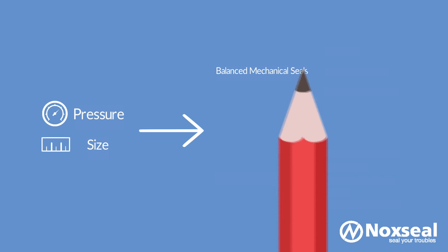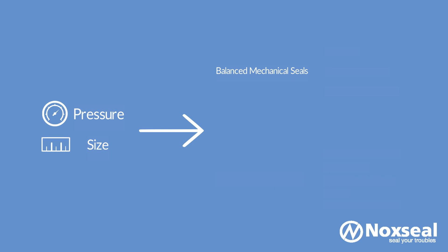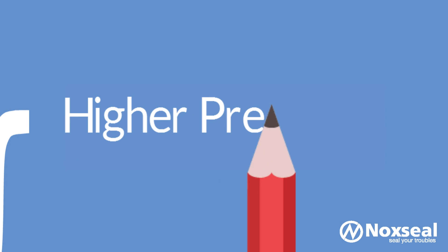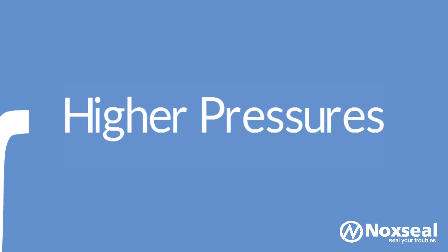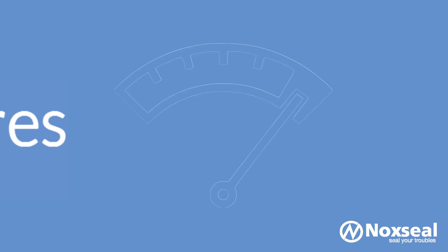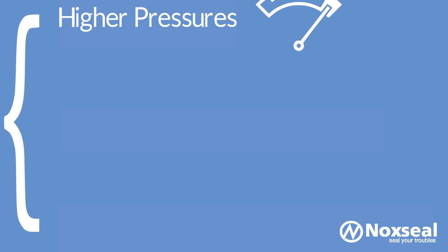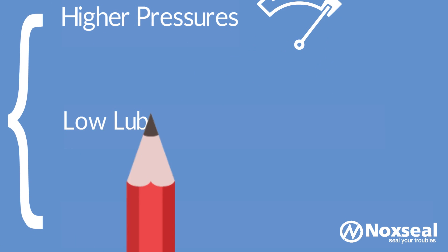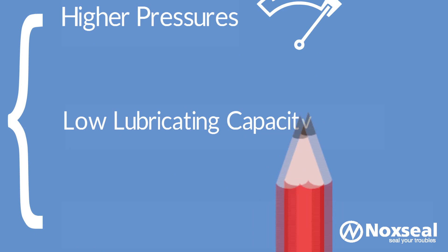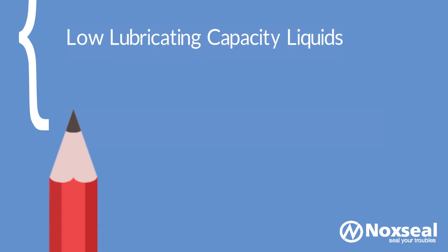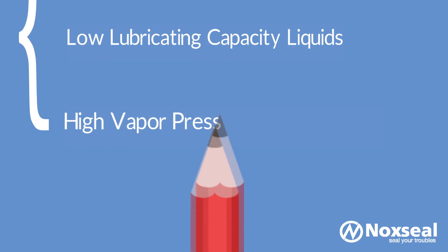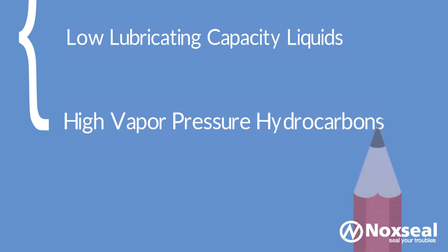Balanced mechanical seals have the ability to sustain higher pressures across the faces and they generate lesser heat. So they are suitable for handling liquids that have low lubricating capacity and hydrocarbons that have high vapor pressure.